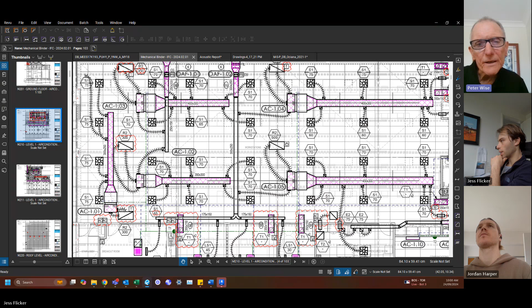I didn't want to create alarm, I'm just trying to make you aware that you've got another noise source to that room. So if that's the situation, just have a look at that as well. If you're comfortable with it, that's fine. You can check the net noise level of that fan, and you've got a fair bit of duct anyway, so you'll get some attenuation from that. Yeah, so it should be okay.